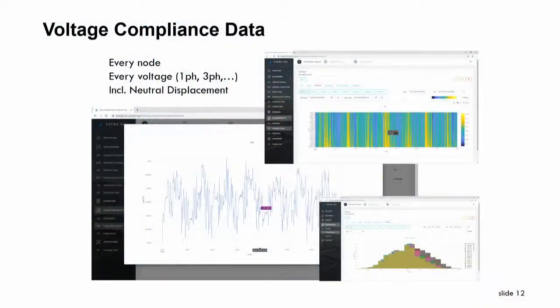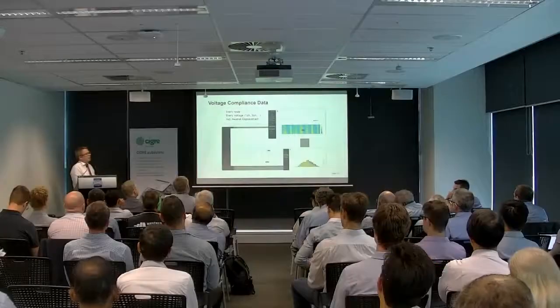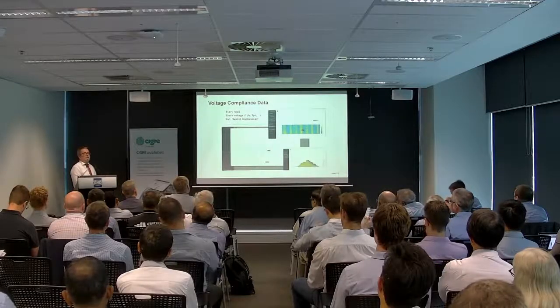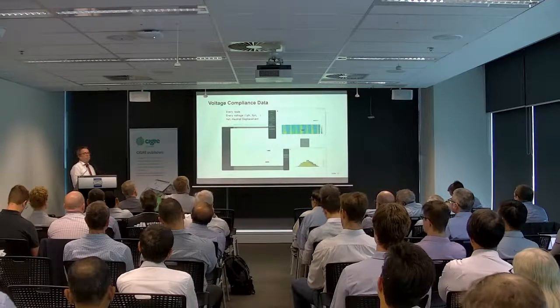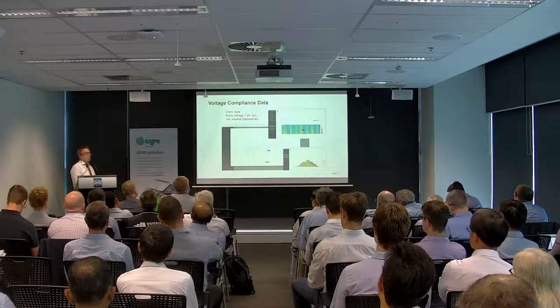You can also run a kind of compliance test, evaluating where in your network you might be outside the statutory limits, and calculate the statistical distribution of it. As I said, the engine underneath this project is a 4-wire implementation, so you get full 3-phase and neutral displacement - not so important at MV level, but in low voltage networks it's extremely important, because the neutral can be quite shifted under unbalanced conditions.